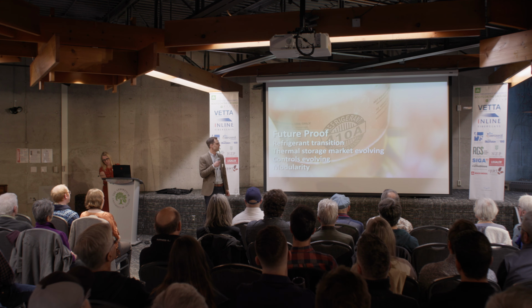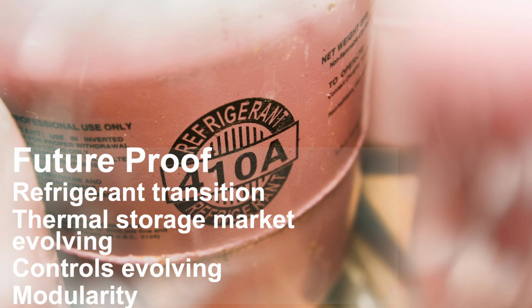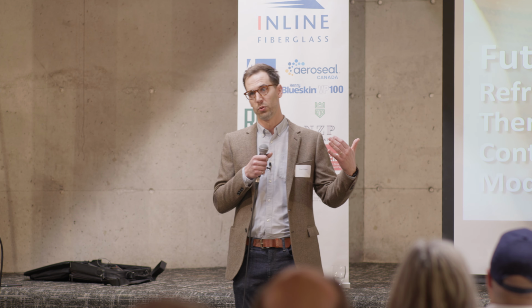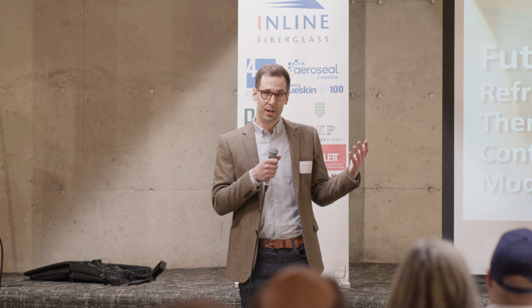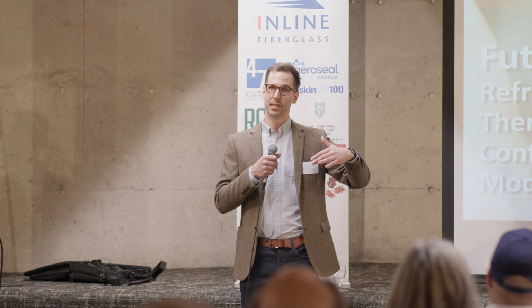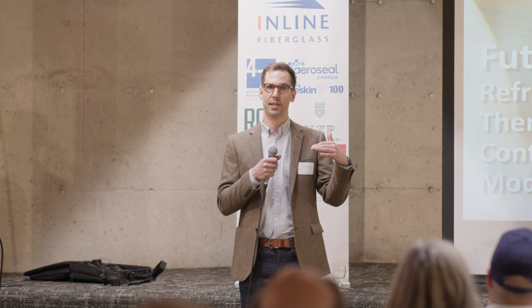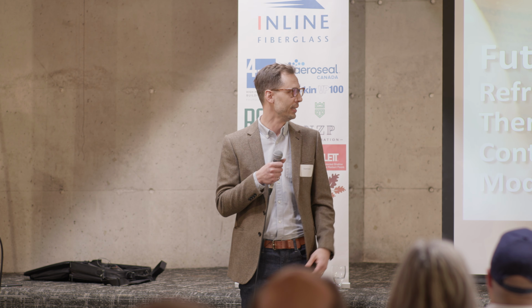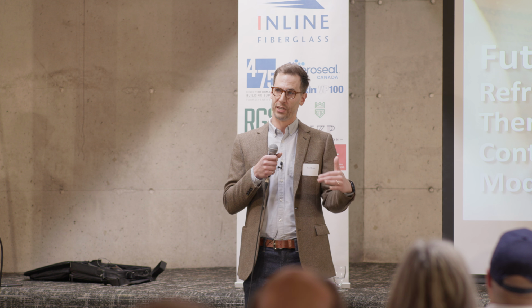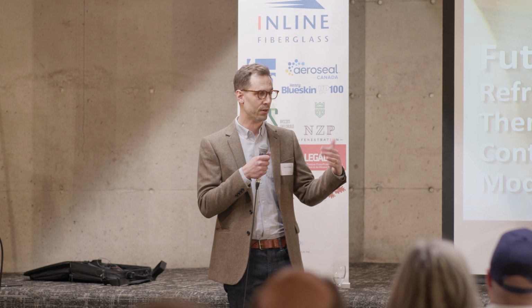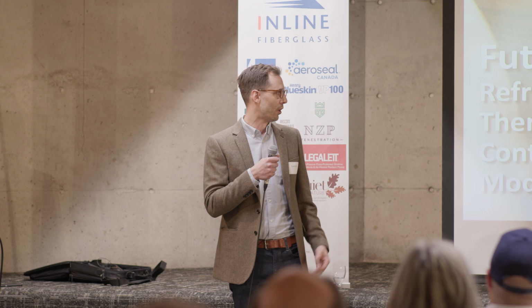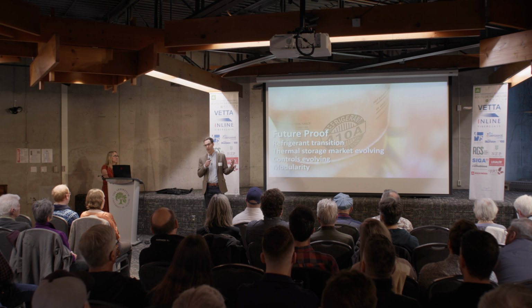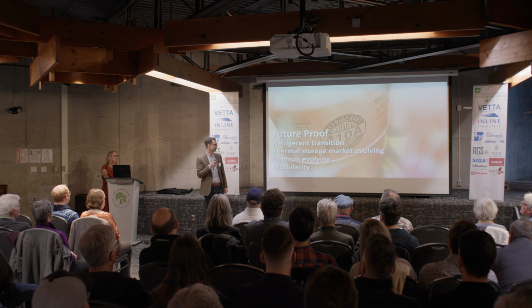So then the future proofing aspect, we're in the midst of a refrigerant transition. You're all probably aware of the Kigali agreement, or amendment I should say. We are phasing down the R410A that has dominated all of our refrigerant systems in homes for the last 20 years or so, because it has very high global warming potential. We've reached this point of stepping stone technologies, stepping stone refrigerants that have lower GWP but higher flammability. And our long game is to get to natural refrigerants like CO2 or R290 propane, which are already kind of dominating the market in Europe.